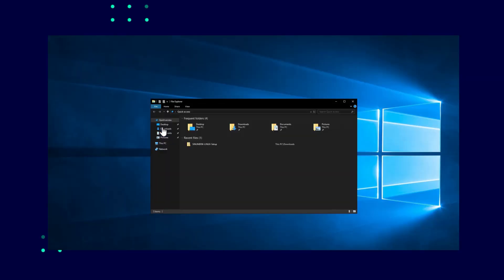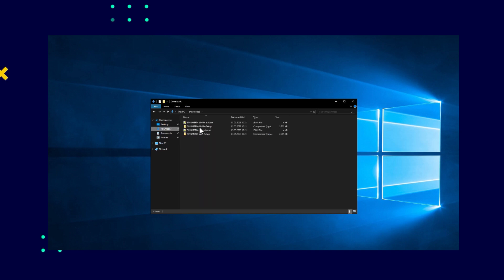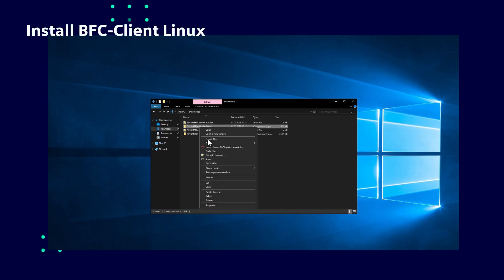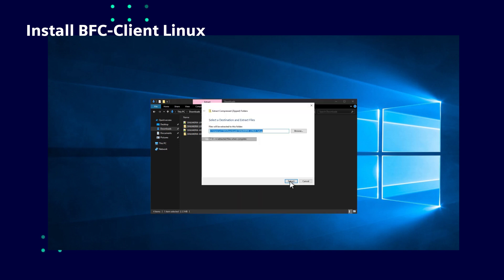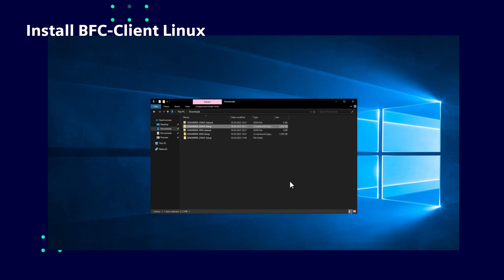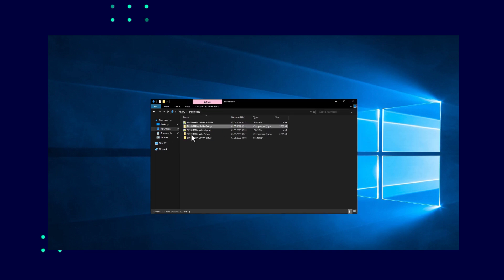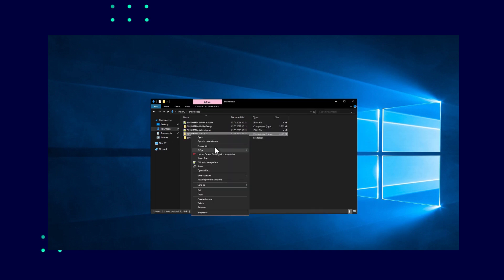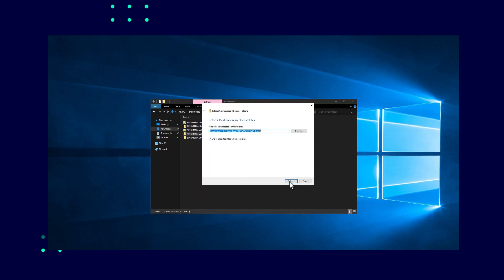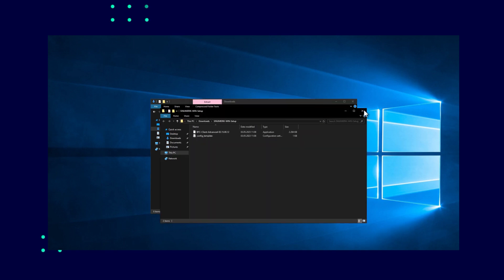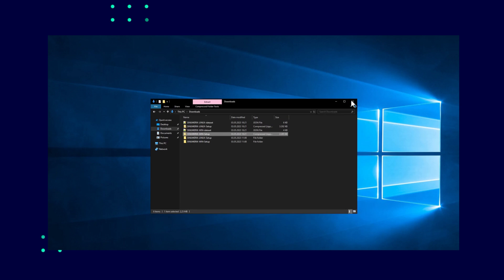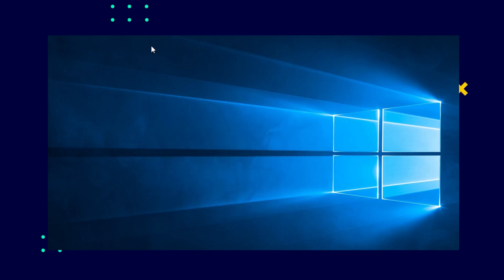Files previously downloaded from the starter wizard contains the BFC client. This must be transferred to the Sinumerik controller in order to establish a connection. To do this, you need software such as WinSCP or another SSH client which must be installed on the Sinumerik controller. The BFC client is in the zip folder with the selected controls name. The folder must be unzipped.